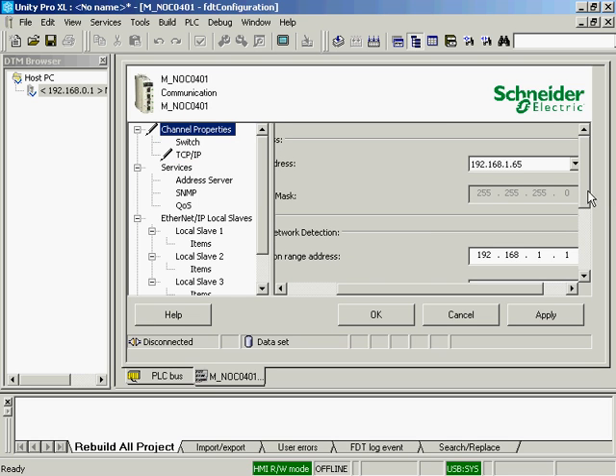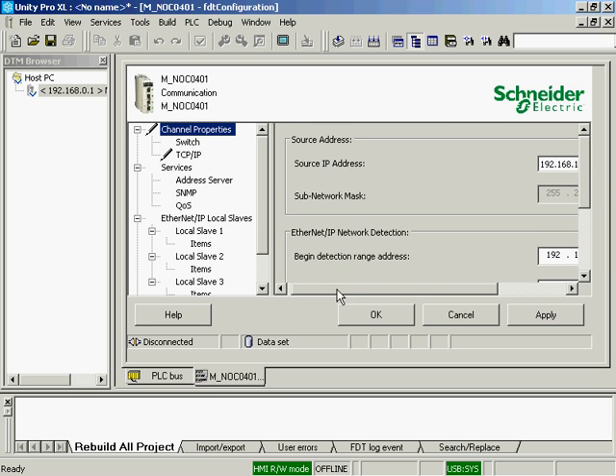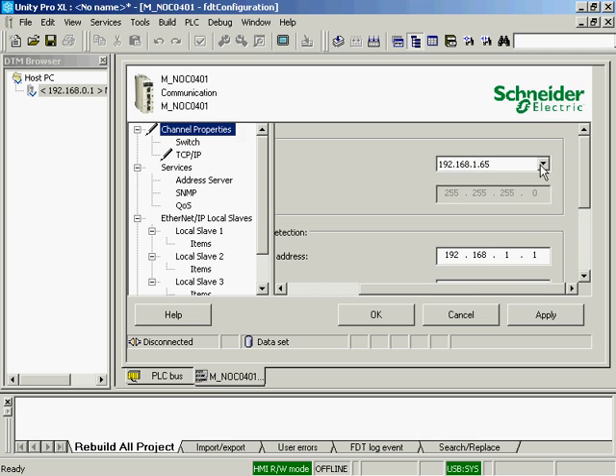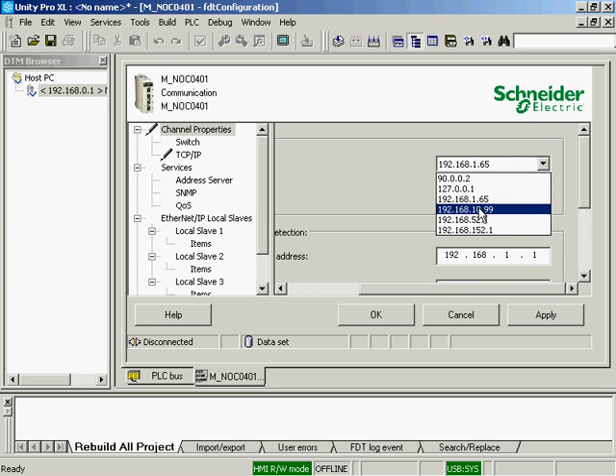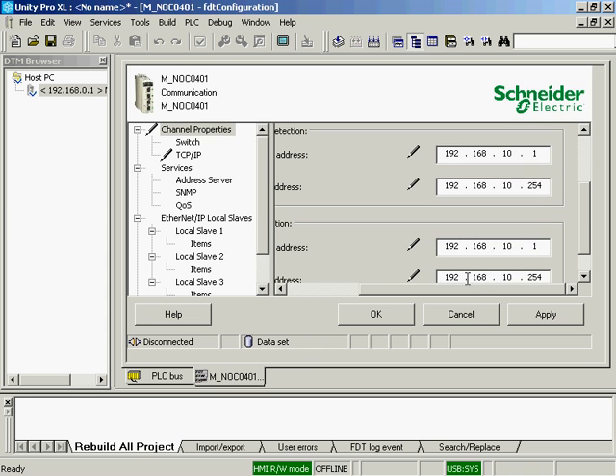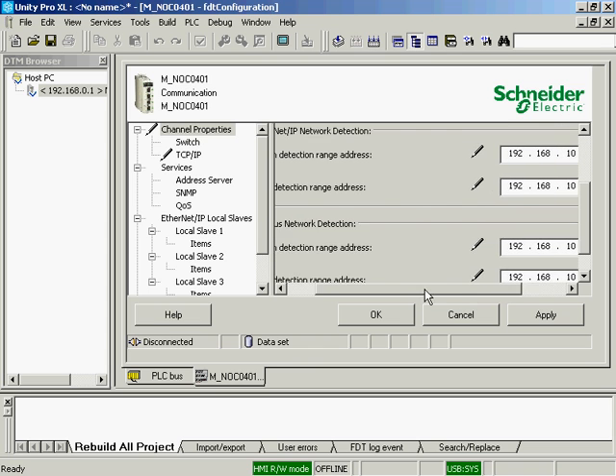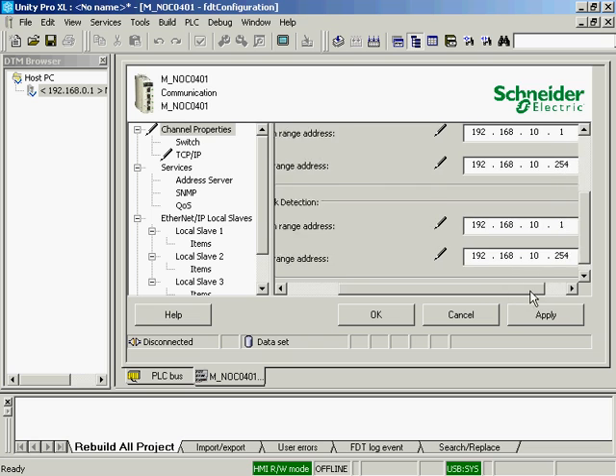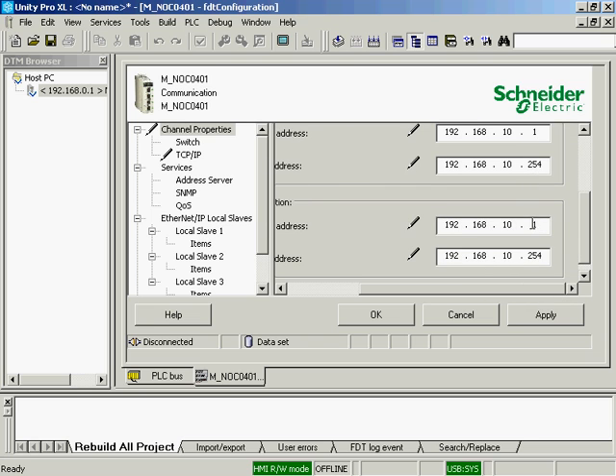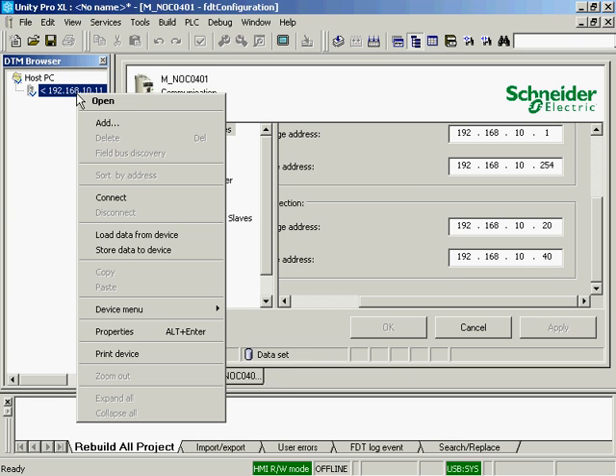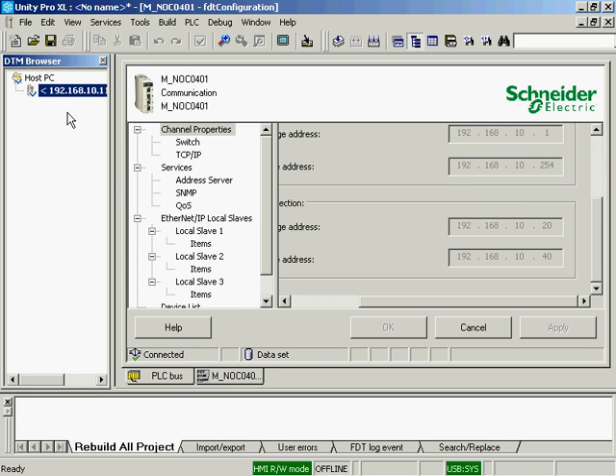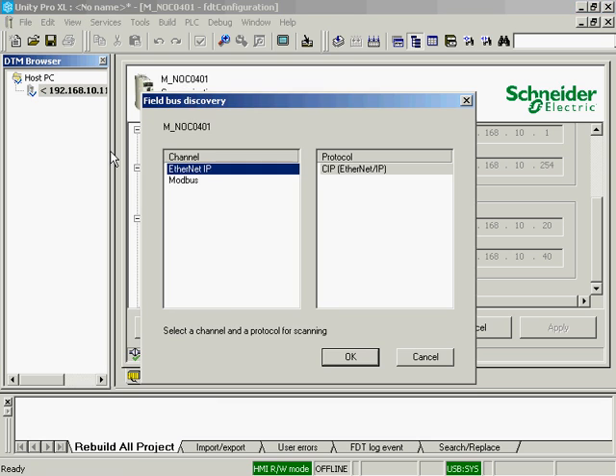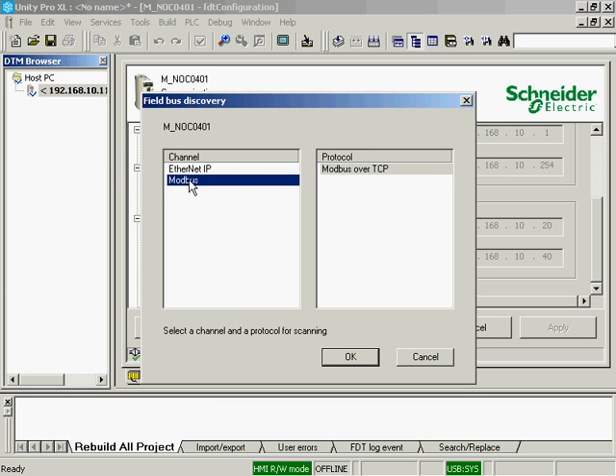Change the channel properties. The source address is going to be the IP address of my computer, which is 192.168.10.99. And then we're going to search under Modbus because we are using the Modbus TCP portion. I'll just search from 20 to 40. The IP address of the drive is 30, but we can do a search. I'm going to apply those changes. The next step is I'll connect. Right-click on the NOC module and connect. Right-click again on the NOC, and we'll do a field bus discovery.